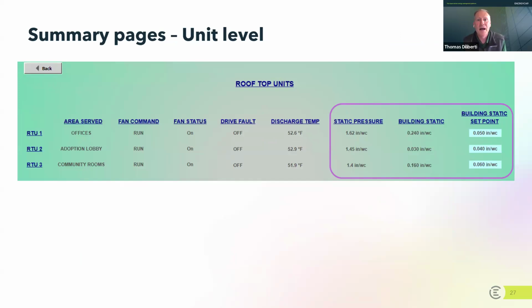Taking a look at this unit level page. I just thought it was a nice little screenshot of a couple rooftop units. So it's looking at static pressure. And one of the things that's a little bit inconsistent here is some of these values, this set point, these are extraordinarily low. These don't really match, and the static pressure is much greater. And so this is another one of those energy opportunities. And this may or may not involve overuse of energy. The biggest thing is there's inconsistency here that I would flag and bring to my attention. And I would try to figure out what's going on here because these numbers, again, don't match these other values.